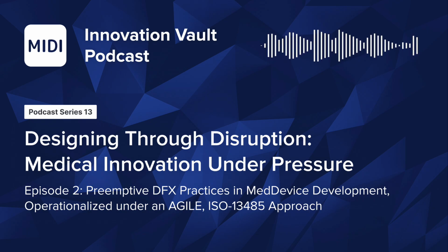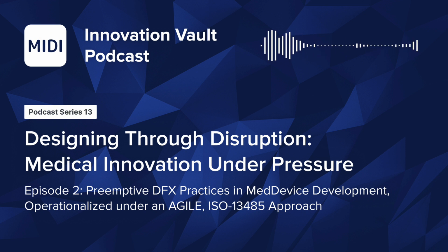Now, let's unpack the next aspect of DFX, and that is DFT and DFU, meaning design for testability and design for usability. Realize that when deploying under Agile, frequent design iterations are encouraged early and often so that you de-risk, or as some people call it, quote unquote, fail early and fail often. So when operationalizing this under ISO 13485, the development team needs to keep tight control and tracking of its design control documentation, where they list system requirements, distill the requirements down into multiple design inputs, then track those inputs to verification and validation parameters of the design.